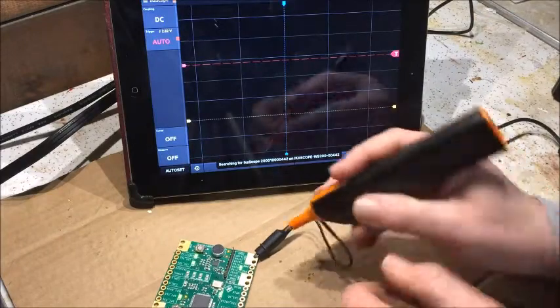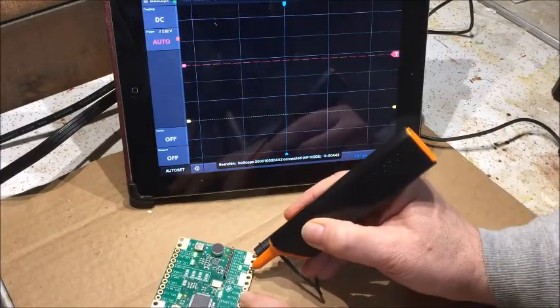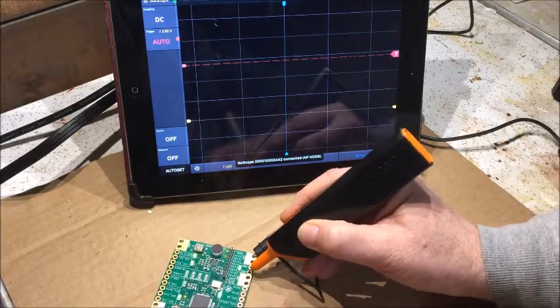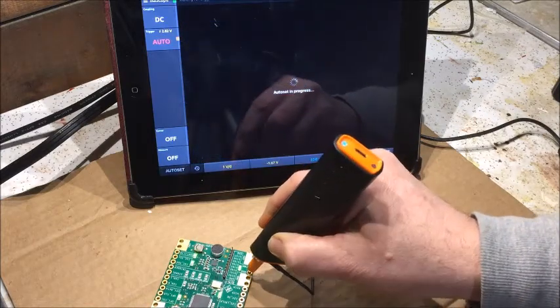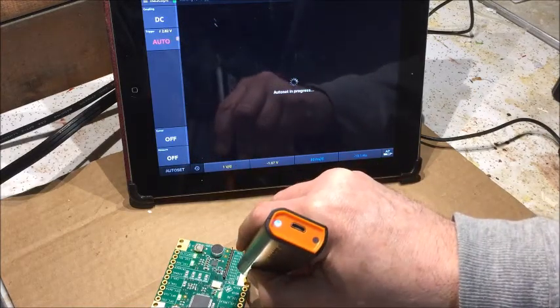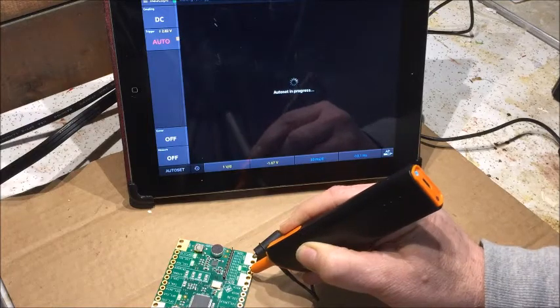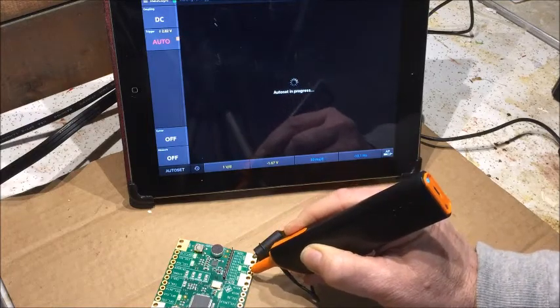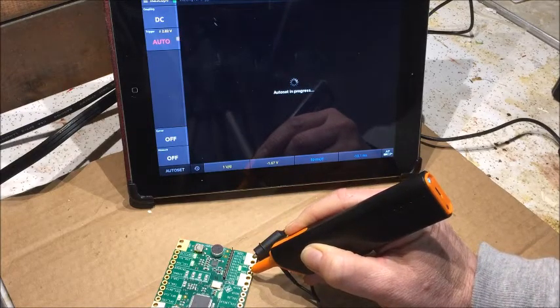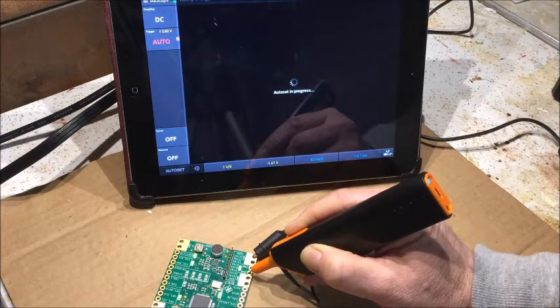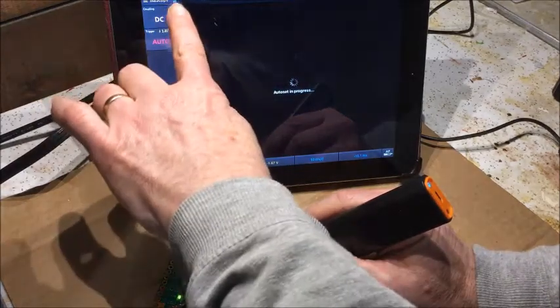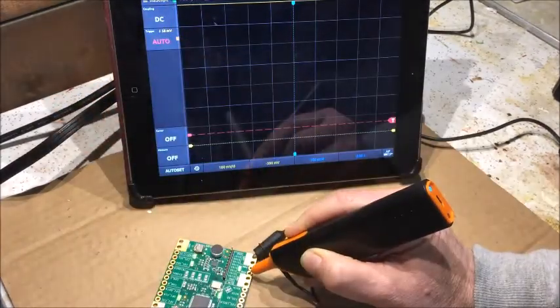Now let's go look at that signal. I'm going to put my probe on here. You notice when I touch it, it does nothing. You've got to apply a little pressure and now you should see that flashing. The auto-set is working. Let's see if it can find this signal.